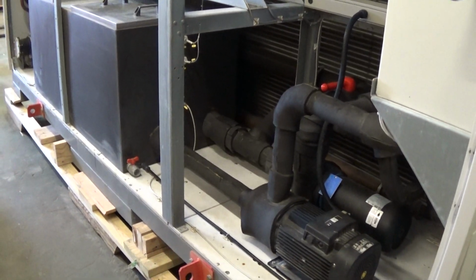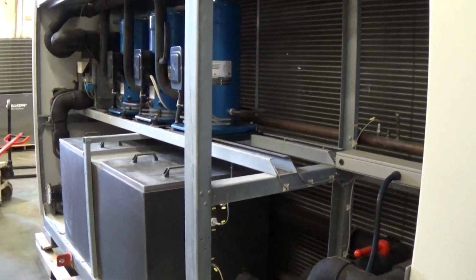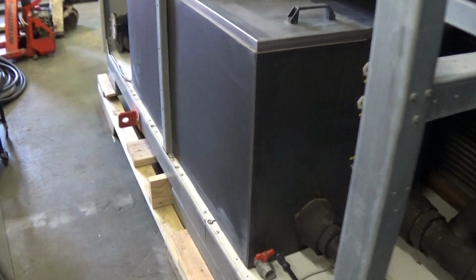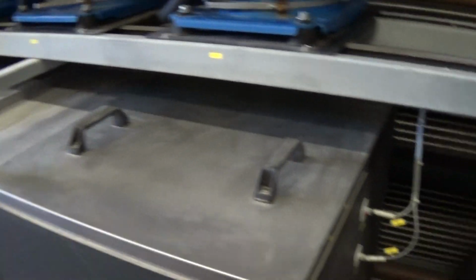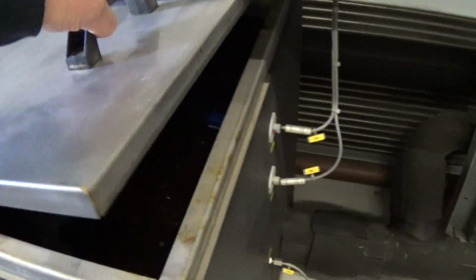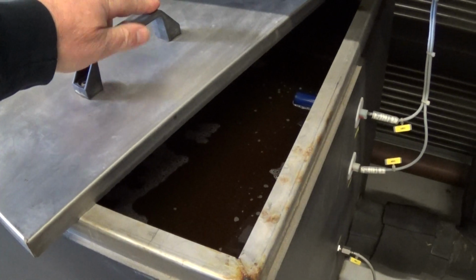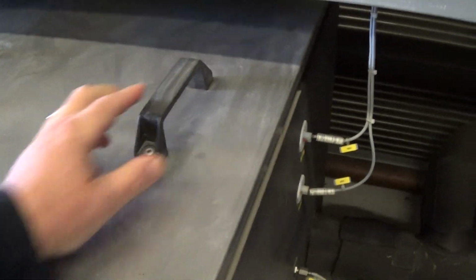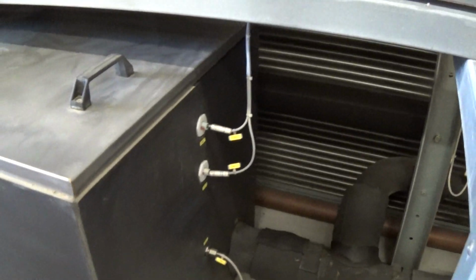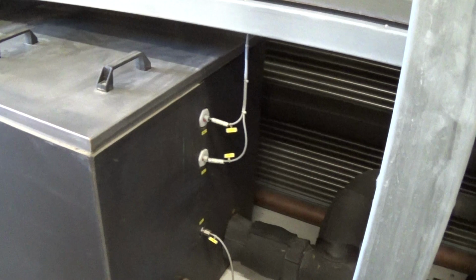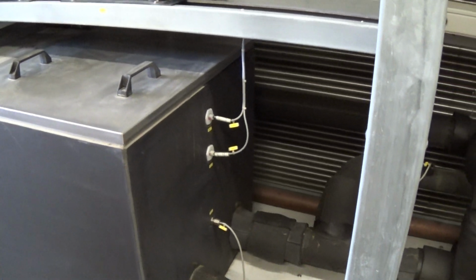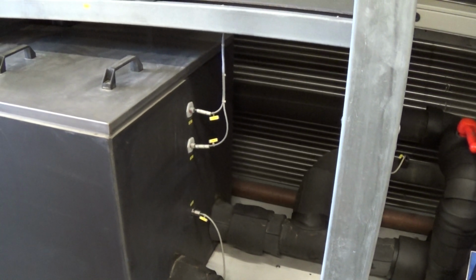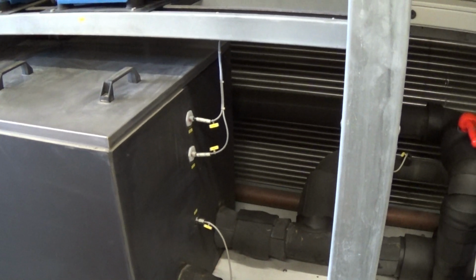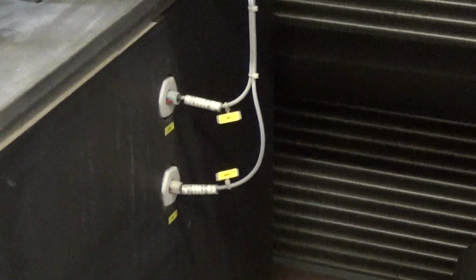alarm. So this is a nice packaged chiller, meaning we have a stainless steel insulated glycol reservoir here, and we've been running and testing this with about 40% glycol concentration. It's going to go to a home in New York State, so that's about what we would recommend for an outdoor chiller there, 40% glycol concentration. The tank has its high level and low level float switches there.